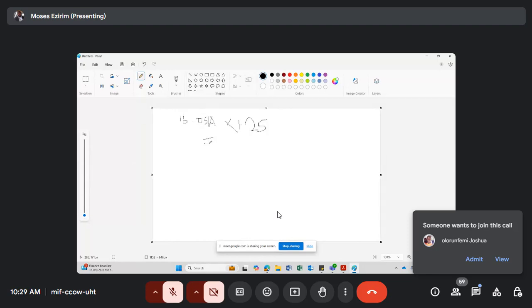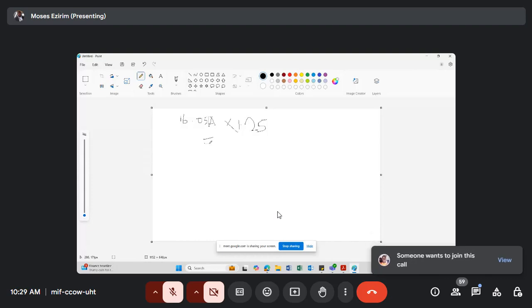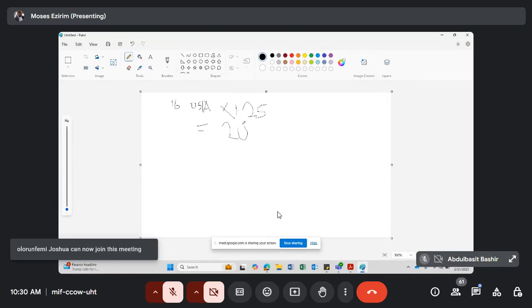So the reason why I put that 1.25 is simply because if you are using a formula to calculate, that is where we're going to see that. So let's multiply - when you multiply 16.05 times 1.25, what will you get? You get 20 now, 20 amps, right? Yes. All right, good.